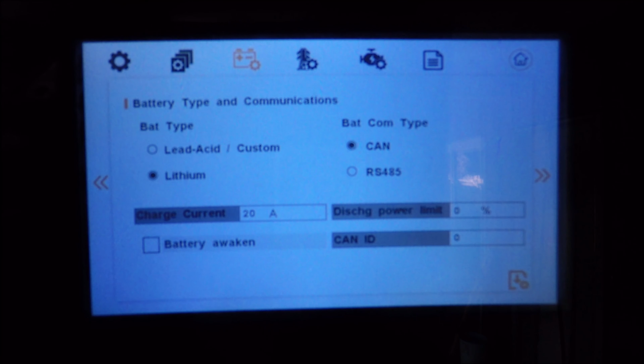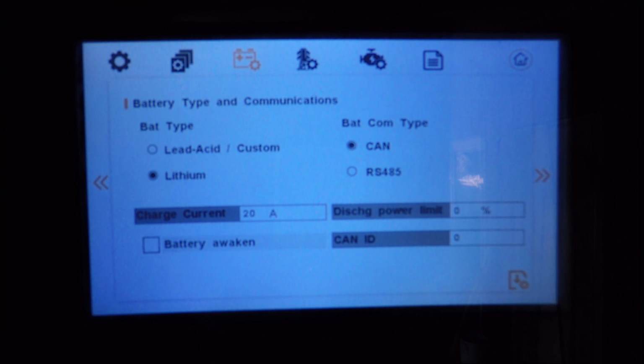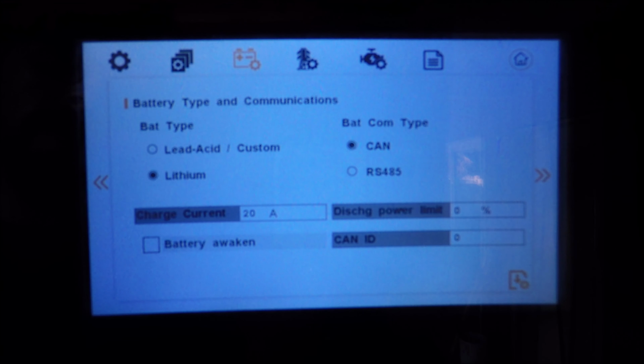Once you have set lithium and you've made the connection, you want to ensure that your batteries are compatible with the inverter. Most batteries have settings in them to help you select a compatible communication type. You can use Pylon Tech or DEYE to communicate with the inverter. I'll flash on the screen the communication type that the inverter prefers. Next, we'll cover battery setup.